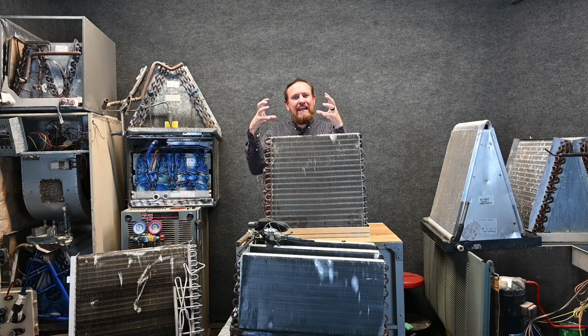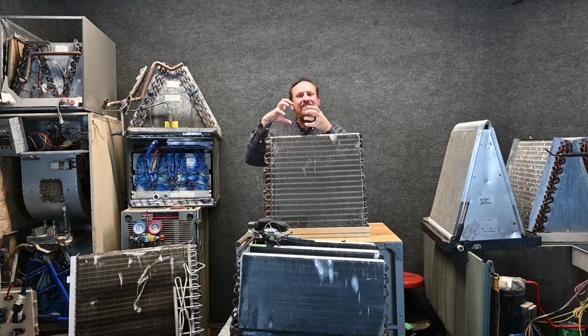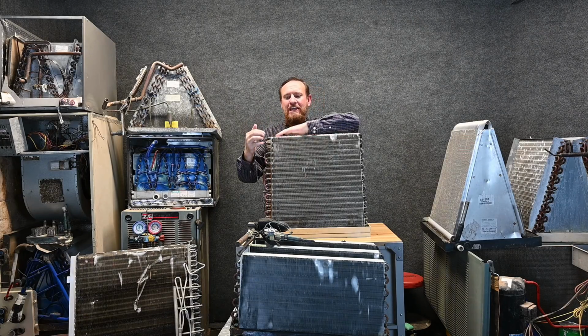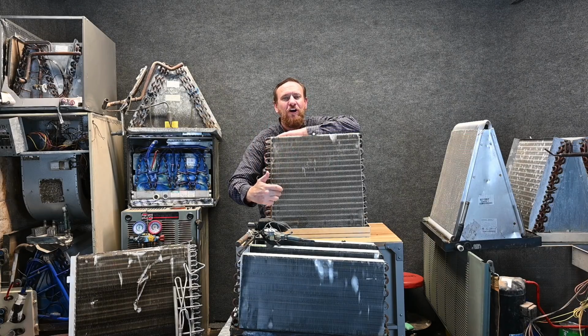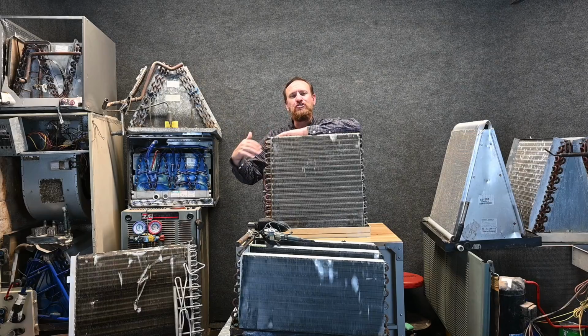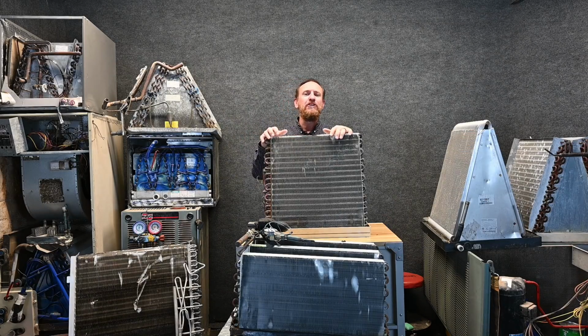And if the refrigerant's below dew point temperature, as the air is coming through this evaporator coil, the moisture will condense. In other words, the air is cooled, the air gets squeezed, and as it's being squeezed, it will overflow the moisture out of the air. And the moisture will collect on these little fins, and then it will ride these fins all the way down into this drain pan till we drain it outside. So we're physically removing moisture out of the air.